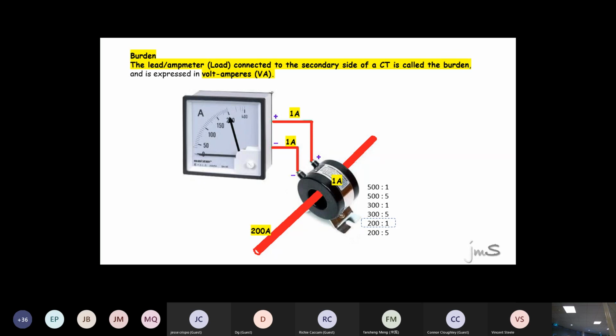Now, what size wire must these two little wires be? 10 mil, 25 mil, or 1.5? I'll give you a hint. Look, it's only 1 amp. So those two little wires running here, we normally make them double insulated wires. Double insulated, and what I've always done is use 2.5. That's all I did because it's easier. You get appliance wire and you get conduit wire. I normally use appliance wire. It's just more flexible and soft, that's all. But again, talk to your boss and see what he wants you to put in if they use it.